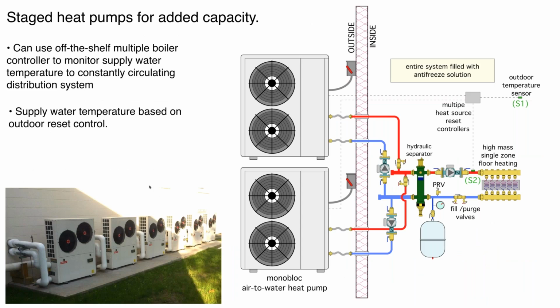And you may be thinking, well, gee, what do I do if I have a higher load than maybe a 4 or 5 ton heat pump? Well, there's options. One option is to get into staged single phase heat pumps. And single phase heat pumps go up to about 5 tons. Beyond that, you're into a 3-phase unit. And they do exist. You can buy 20 ton, 50 ton, even 100 ton air to water heat pumps. Several of the big names in the industry are starting to bring out these commercial size air to water heat pumps. And that's another possibility.